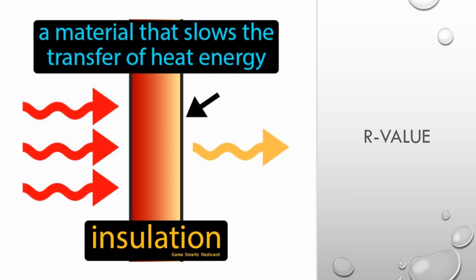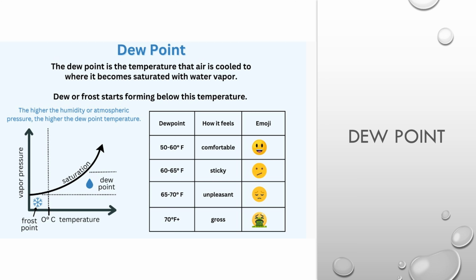All right, so the last factor I want to describe is dew point. Dew point is very hard to understand sometimes. It's just confusing to some people. So if I had a 60-degree dew point, anything below 60 degrees is going to condensate. If I took a can of cold Coke out of a fridge and put it on the counter, there would be condensation on it because that can of Coke is probably 35 degrees Fahrenheit and the dew point is 60.